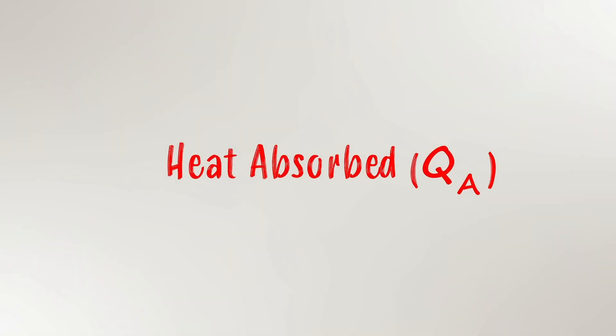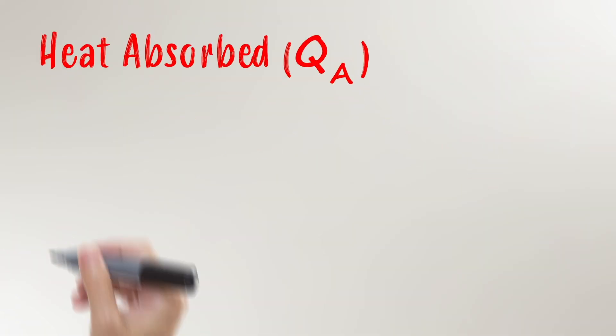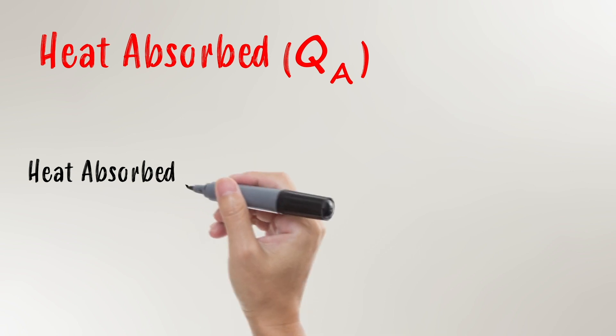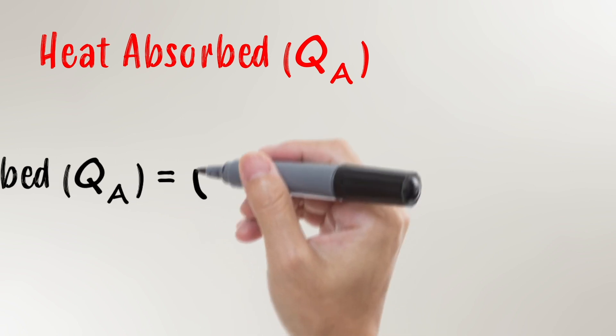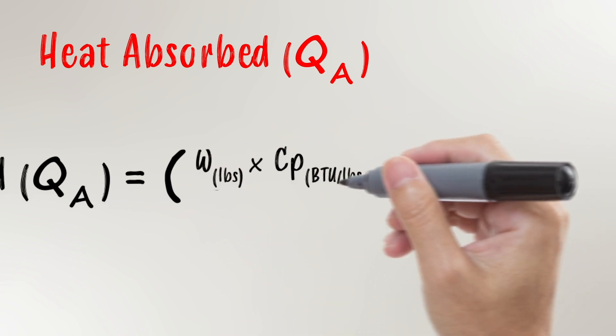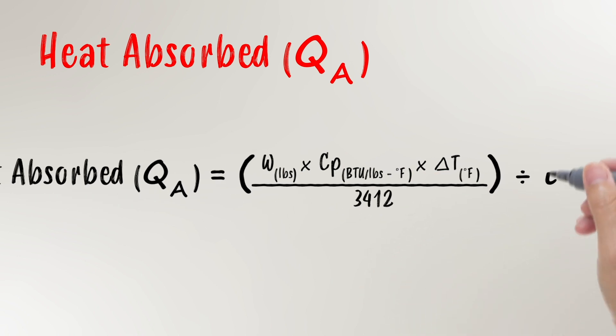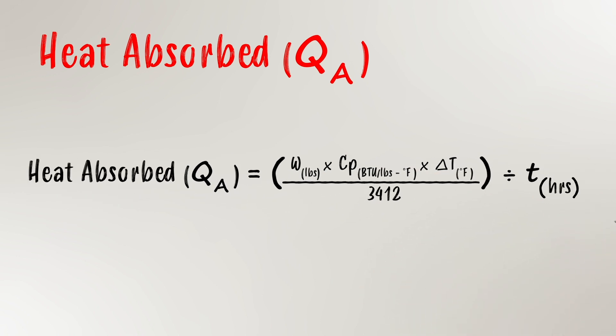The first part of the equation is QA, which is the heat energy absorbed by the materials. Here's the formula: QA equals mass times the specific heat, or Cp, times the delta T — divide that by 3412, which in turn is divided by time. This equation allows us to determine the total kilowatts required for any application.